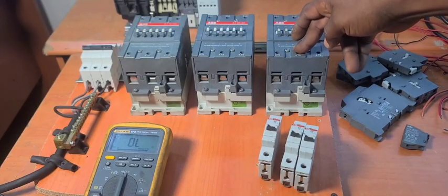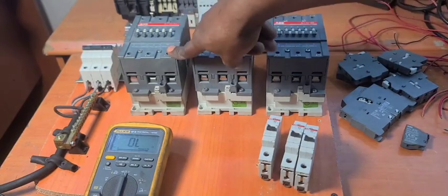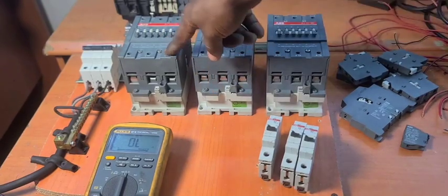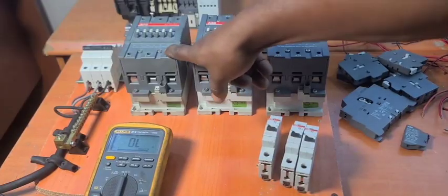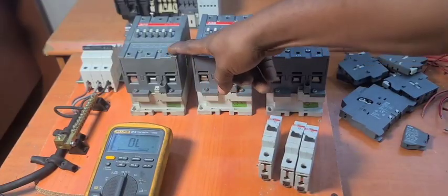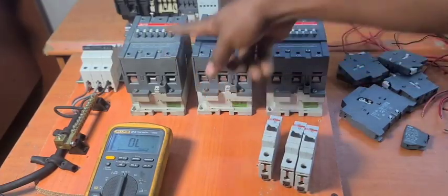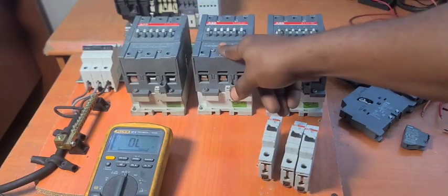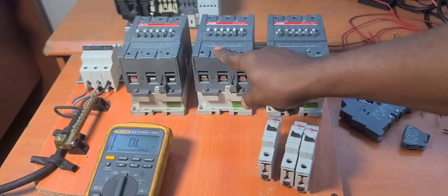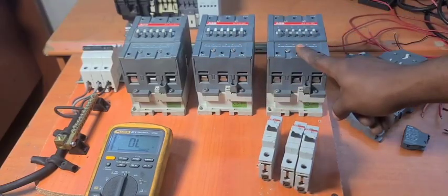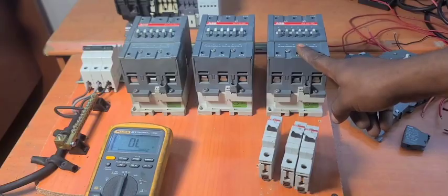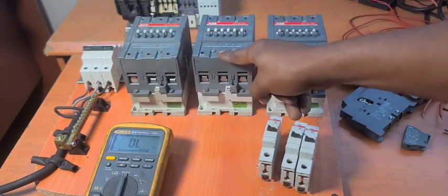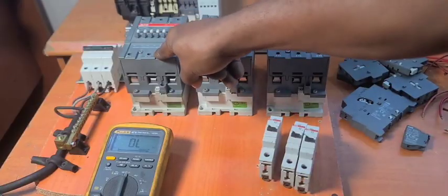So the configuration will be that solar is the priority. That is, the main source of power is solar. So when solar fails, when solar goes out, say in the evening, and when sun sets, we don't have solar that time, mains should take over. Mains will continue, and then if mains fails, generator should take over. And if there is mains and there is solar, mains should be off while solar should continue.